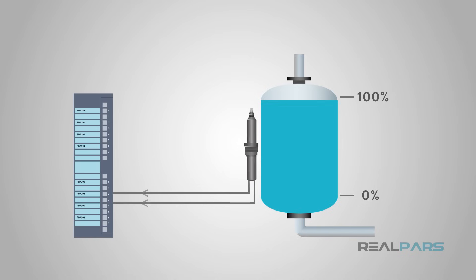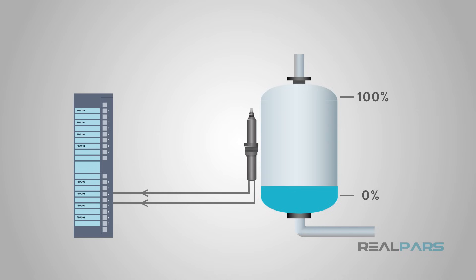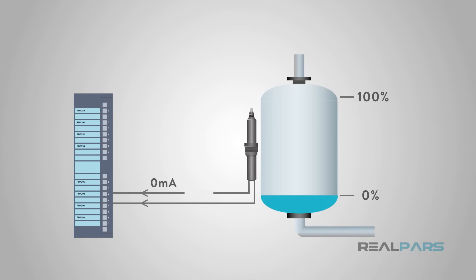Lastly, 4 to 20 milliamp current loop signals provide a basic level of diagnostics. Since 0% equals a 4 milliamp signal, a broken wire would break the circuit, and 0 milliamps would be sensed.